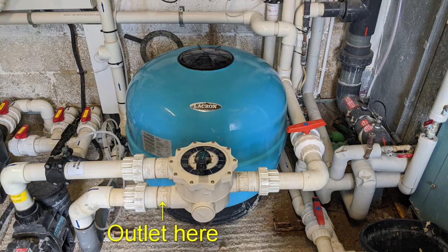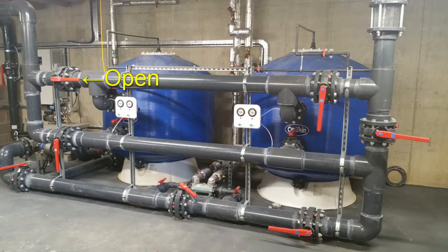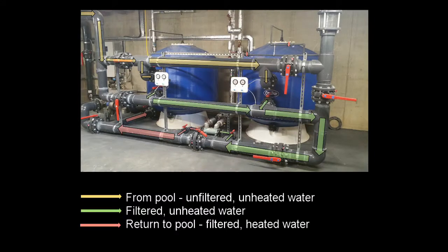identify the outlets. With the valve handles, if you've got butterfly valves, if the valve handle is running parallel to the pipework, then it's in the fully open position. So on that principle, you're able to figure out where water's going and where water's not going. So you can basically continue to follow the path that the water is taking through the system.